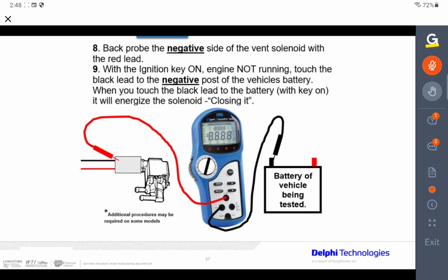There are times you'll want to run extra long leads, or as we talked about this morning, you might want to put a fast blow fuse in the red lead. When you do that, you have to zero it out. That's why that REL or zero function is there, to zero out the added resistance in the circuit.